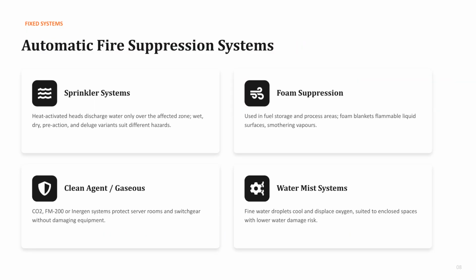Beyond portable units, facility protection often relies on fixed automatic fire suppression systems. Sprinkler systems feature heat-activated heads that discharge water targeted specifically over affected zones, available in wet, dry, pre-action, or deluge configurations to suit different environments. Foam suppression is essential for fuel storage and processing areas, blanketing liquid surfaces to smother flammable vapors. Clean agent or gaseous systems using CO2, FM200, or Inergen protect sensitive environments like server rooms and switchgear without damaging electrical components. Finally, water mist systems produce microdroplets that cool fires and displace oxygen, making them ideal for enclosed spaces where minimizing water damage is critical.